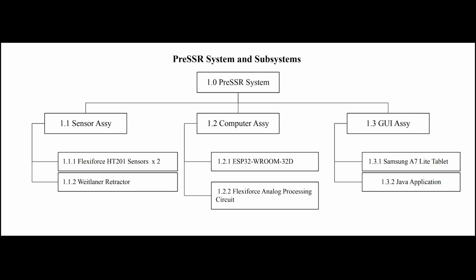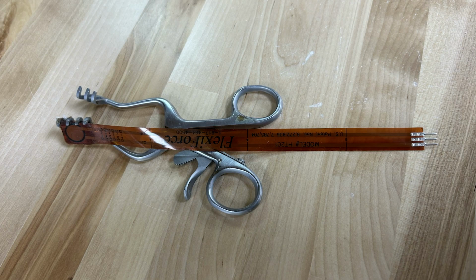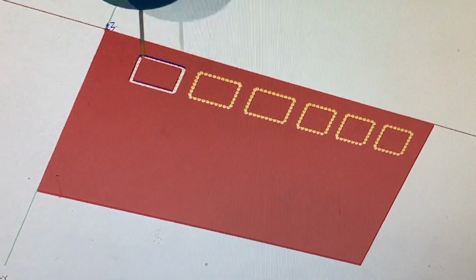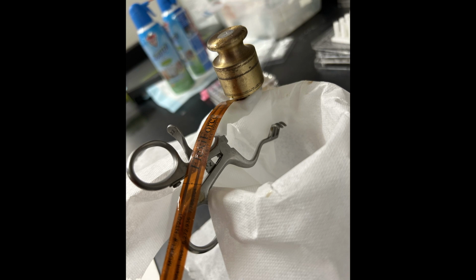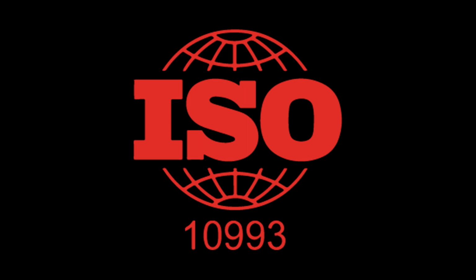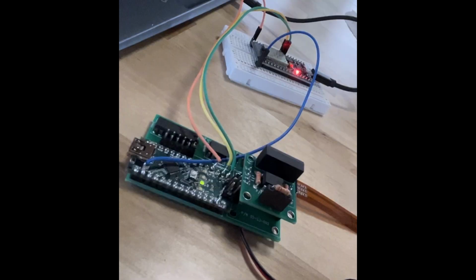The PreSSR system is divided into three sub-assemblies: the sensor, computer, and graphical user interface assemblies. The sensor assembly consists of two Flexiforce HT201 sensors, a Weitlaner retractor to which they are epoxied, and two steel plates on which the force sensors lay flat, all adhered to one another using Masterbond EP2HT2Med epoxy. The sensor assembly is the only sub-assembly that will be in the sterile field of the operating room, and all of its components are thus certified as biocompatible under the ISO 10993-5 standard of biological evaluation of medical devices for cytotoxicity. The computer assembly consists of an ESP32D board and the Flexiforce analog processing circuit.